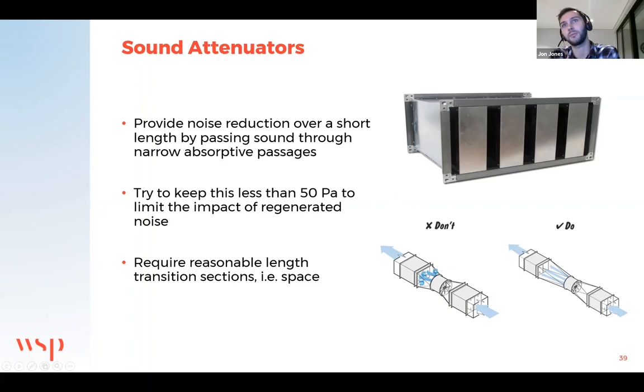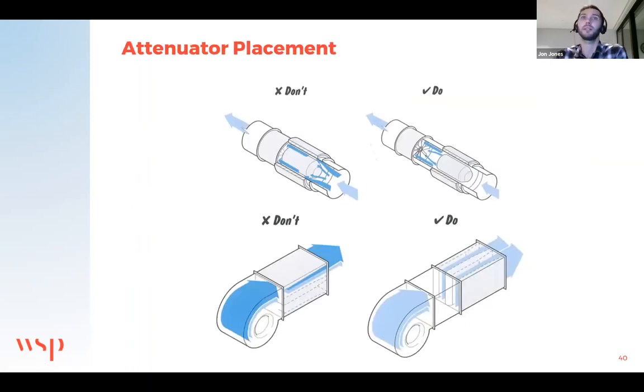setup in terms of the airflow, and air coming off the fan will still be very turbulent before it goes into the attenuator, and this will significantly increase the pressure drop across it. More ideally, as shown on the right, you would have a longer transition section such that you do get this laminar flow across the full face of the attenuator. A couple more examples on there.